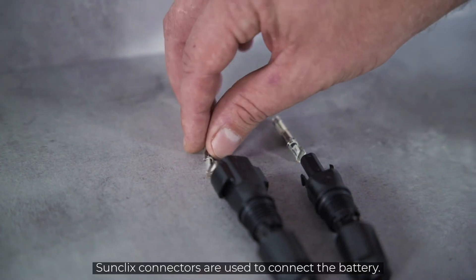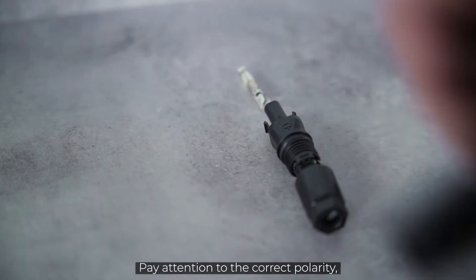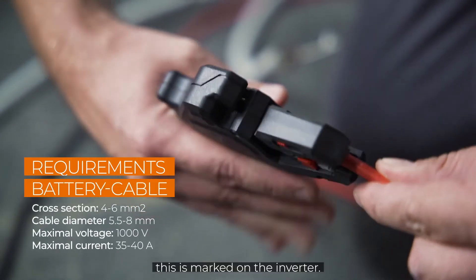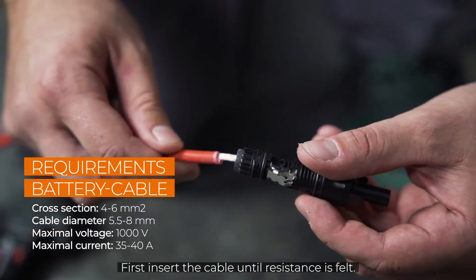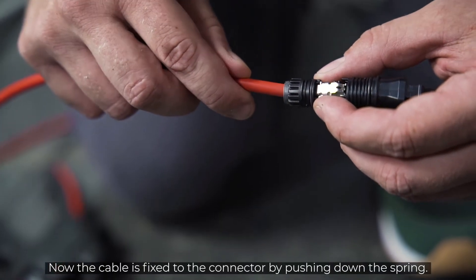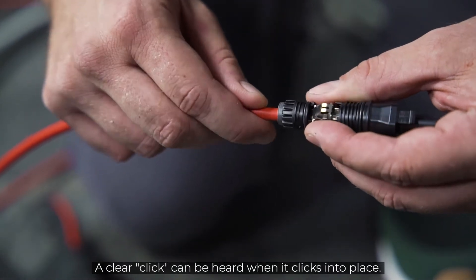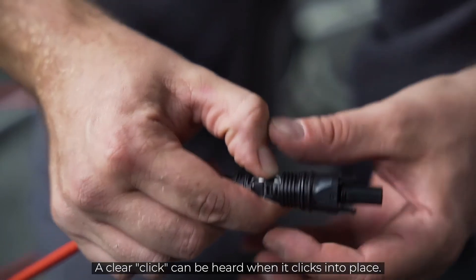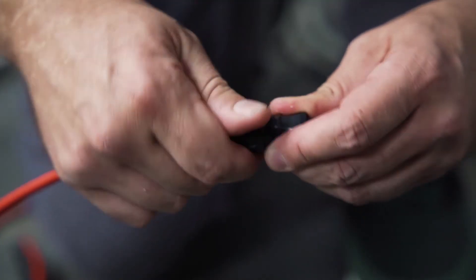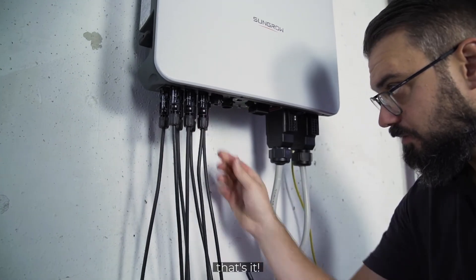Sunclix connectors are used to connect the battery. Pay attention to the correct polarity, which is marked on the inverter. First, insert the cable until resistance is felt. Now the cable is fixed to the connector by pushing down the spring. A clear click can be heard when it clicks into place. Tighten the plug. Plug it in — that's it.